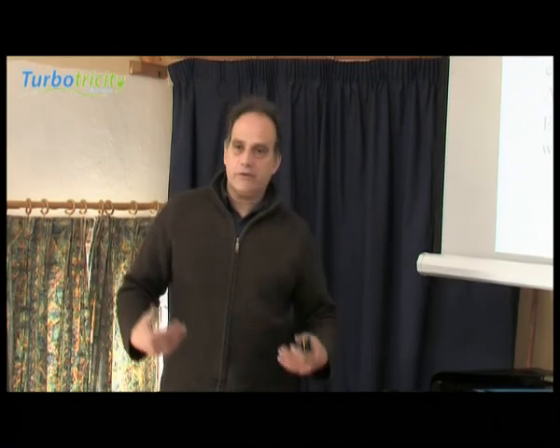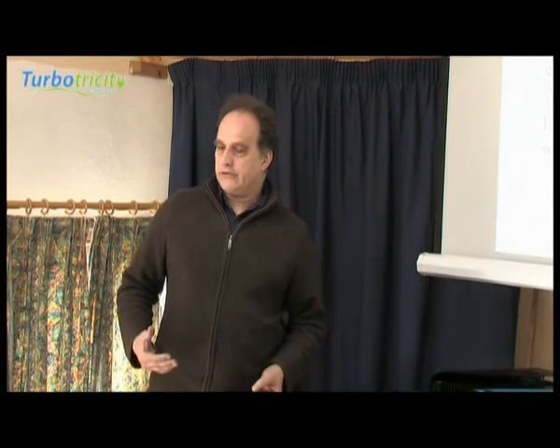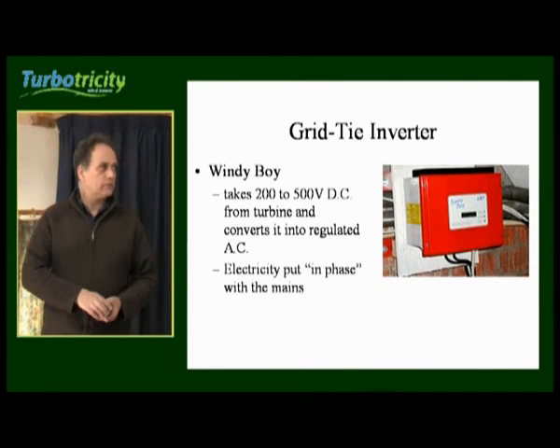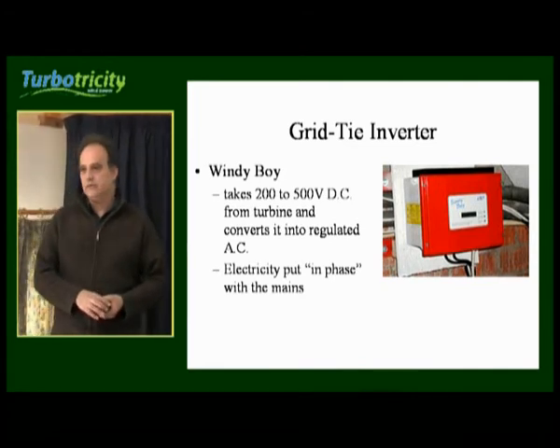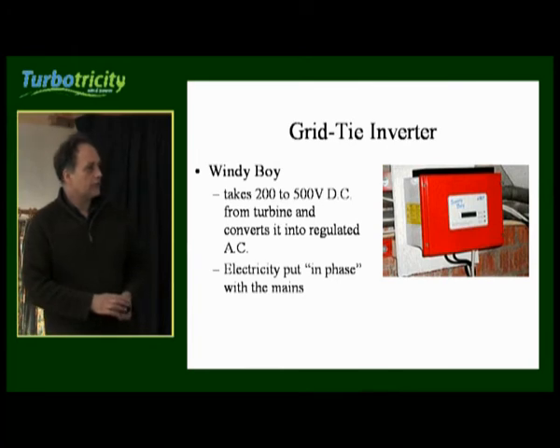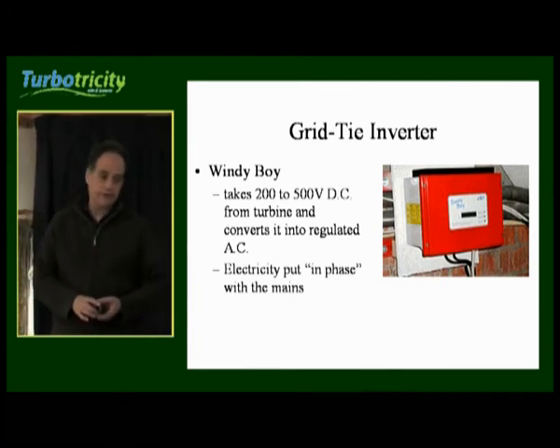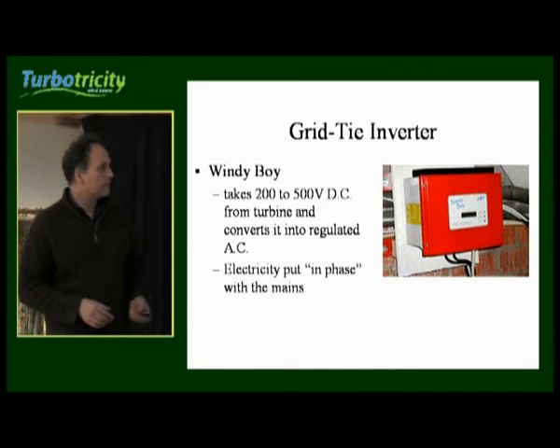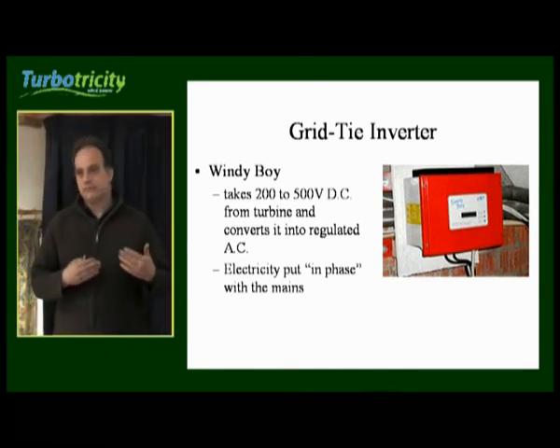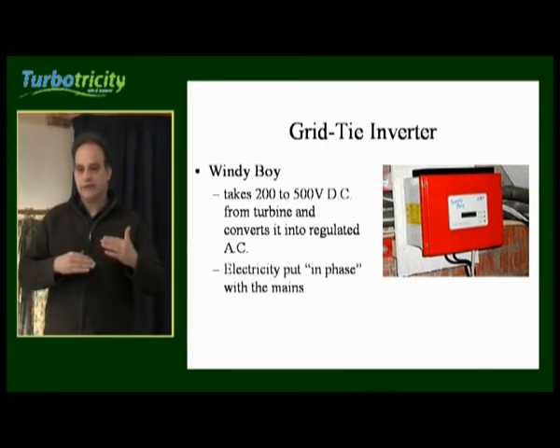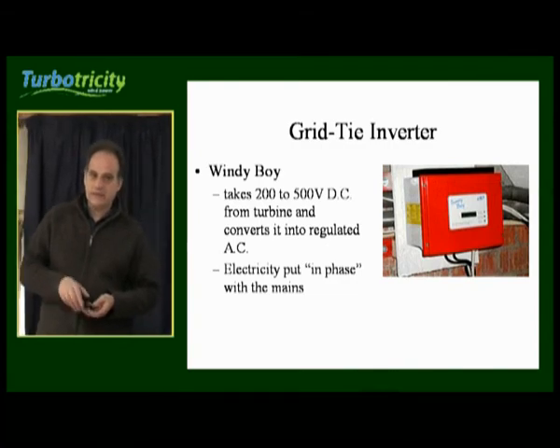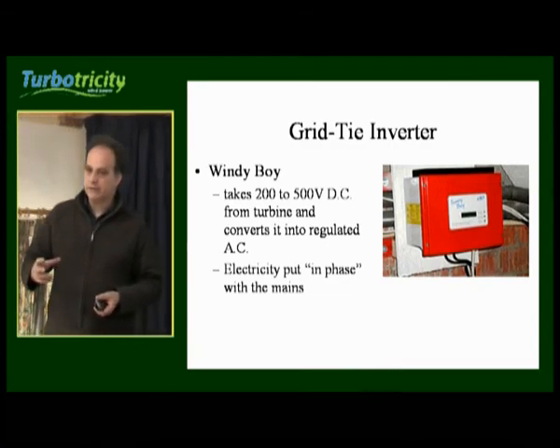Assuming you're not going for a battery system and you're going for a grid-tie system, you'll need a grid-tie inverter. The popular ones on the market are the SMA Windy Boy and Sunny Boy, and also the Aurora ones that we use here. The Windy Boy can take any voltage from your turbine between 200 and 500 volts DC and converts it into regulated AC that is absolutely in phase with the grid.